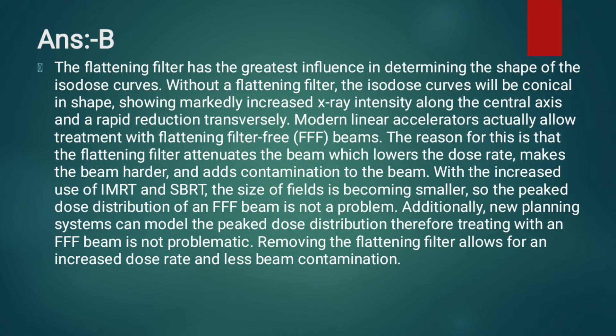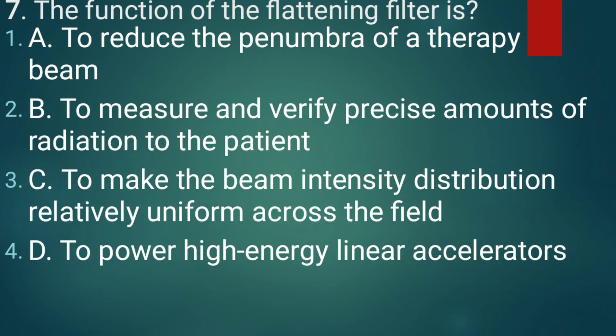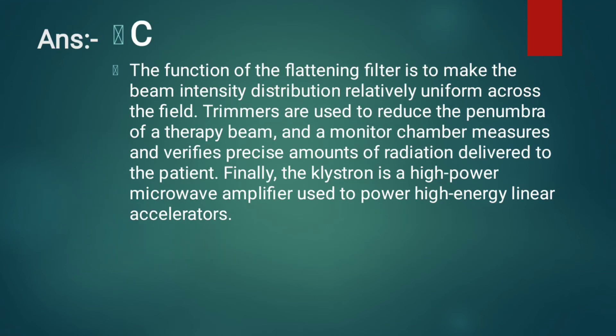Removing the flattening filter allows for an increased dose rate and less beam contamination. Question 7: The function of a flattening filter is? The correct answer is option C: to make the beam intensity distribution relatively uniform across the field. Trimmers are used to reduce the penumbra of the therapy beam, and a monitor chamber measures and verifies the amount of radiation delivered to the patient. The klystron is a high-power microwave amplifier used to power high-energy linear accelerators.